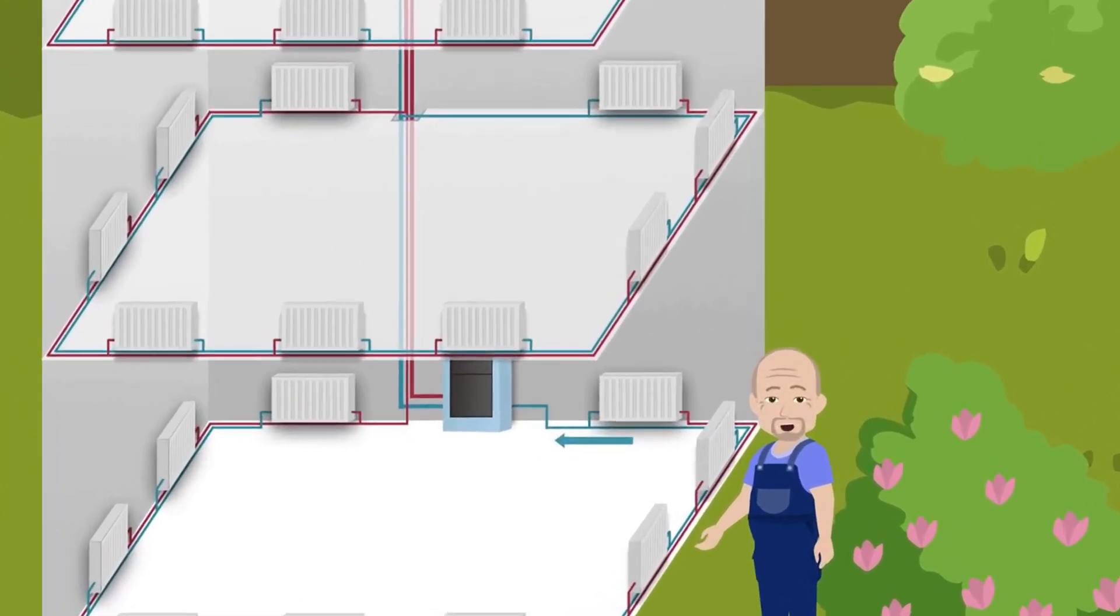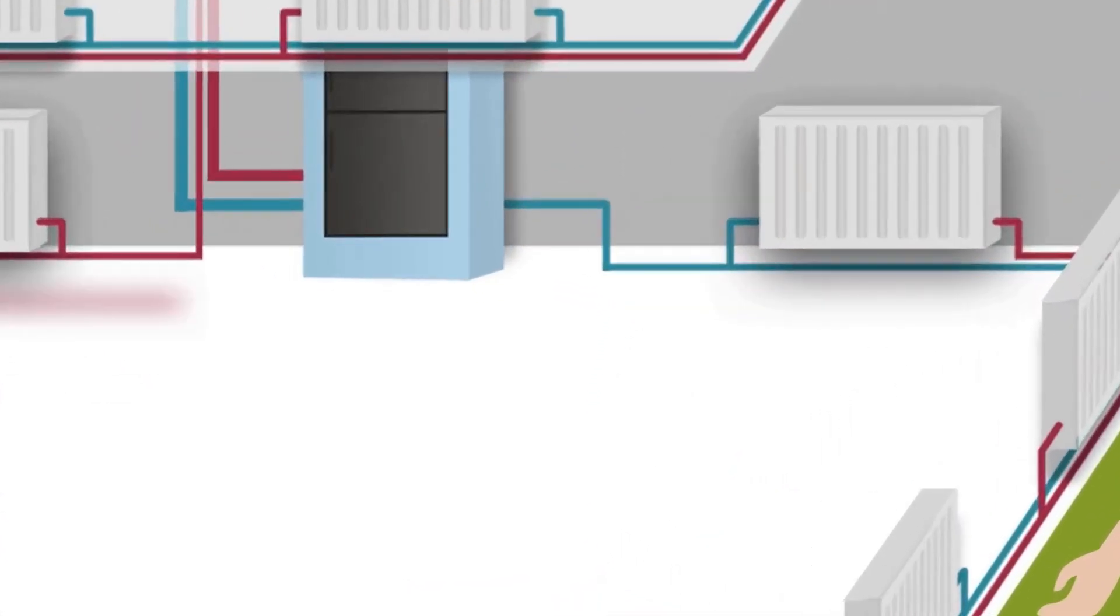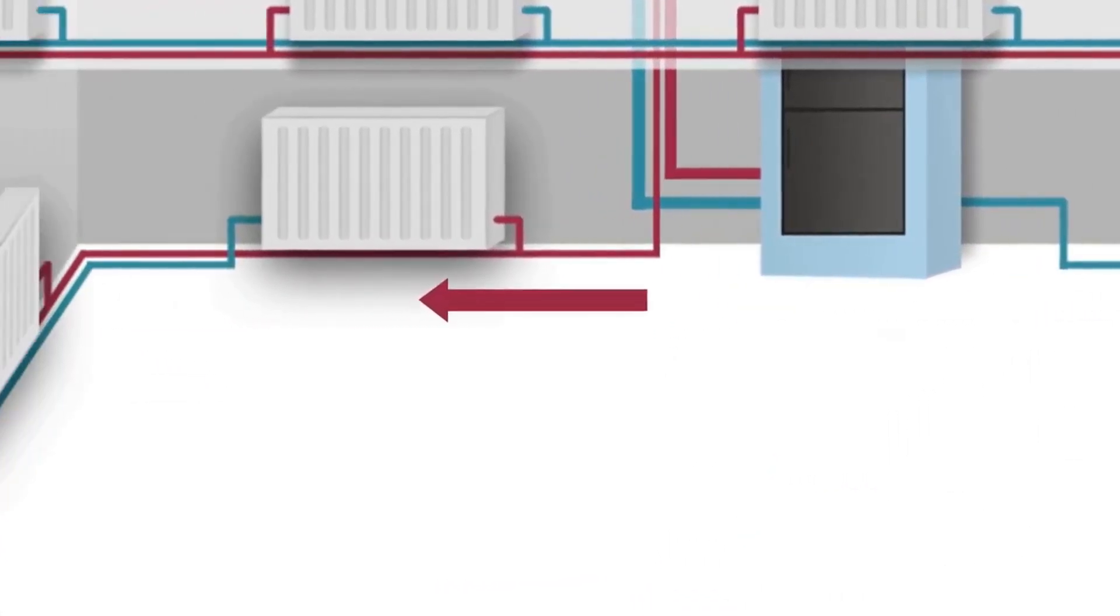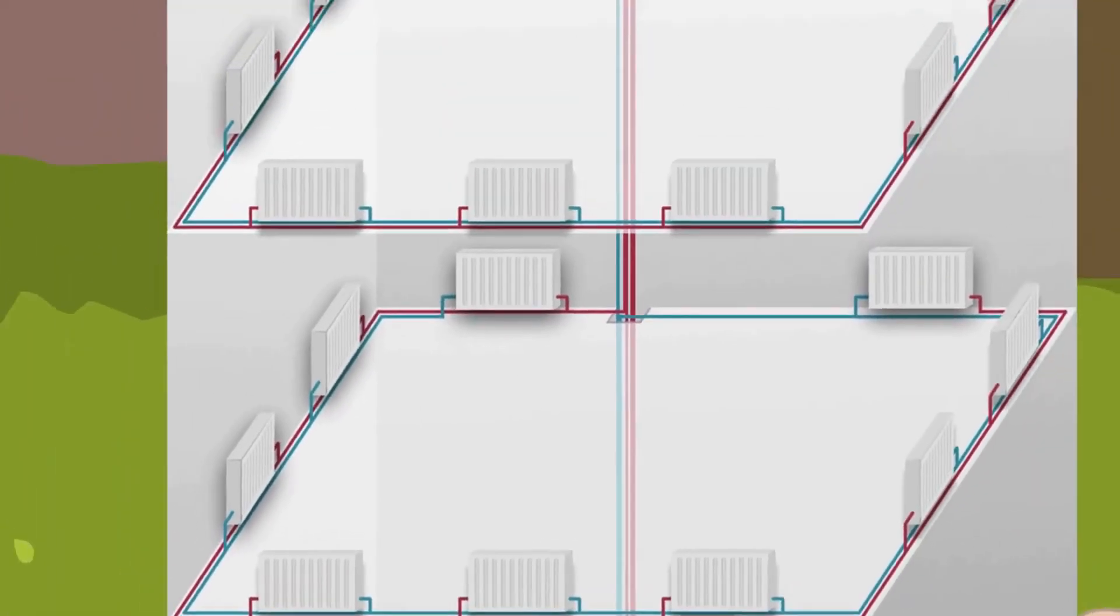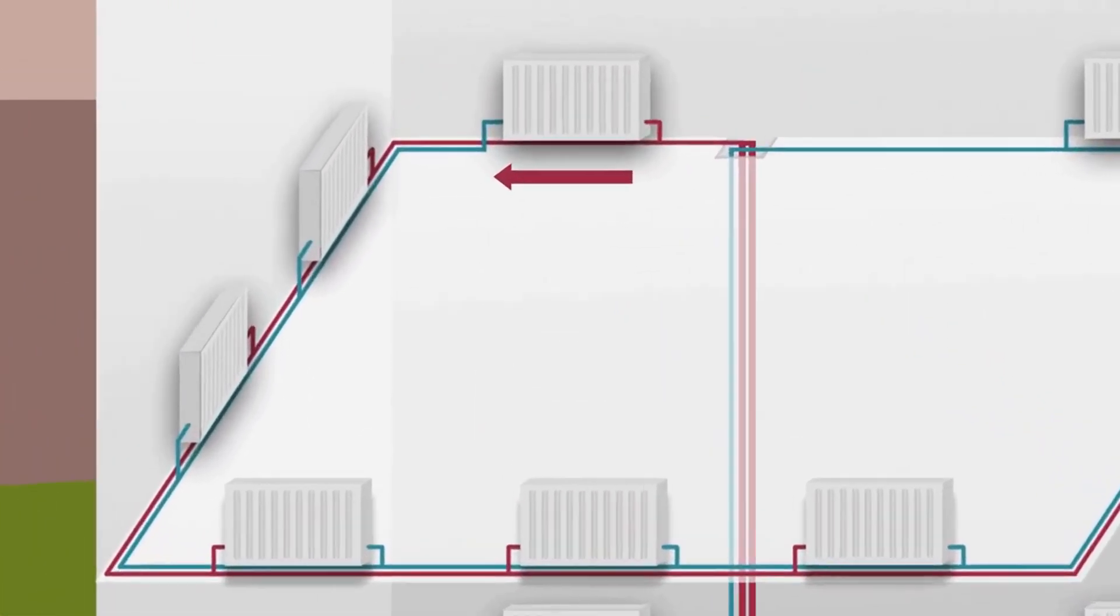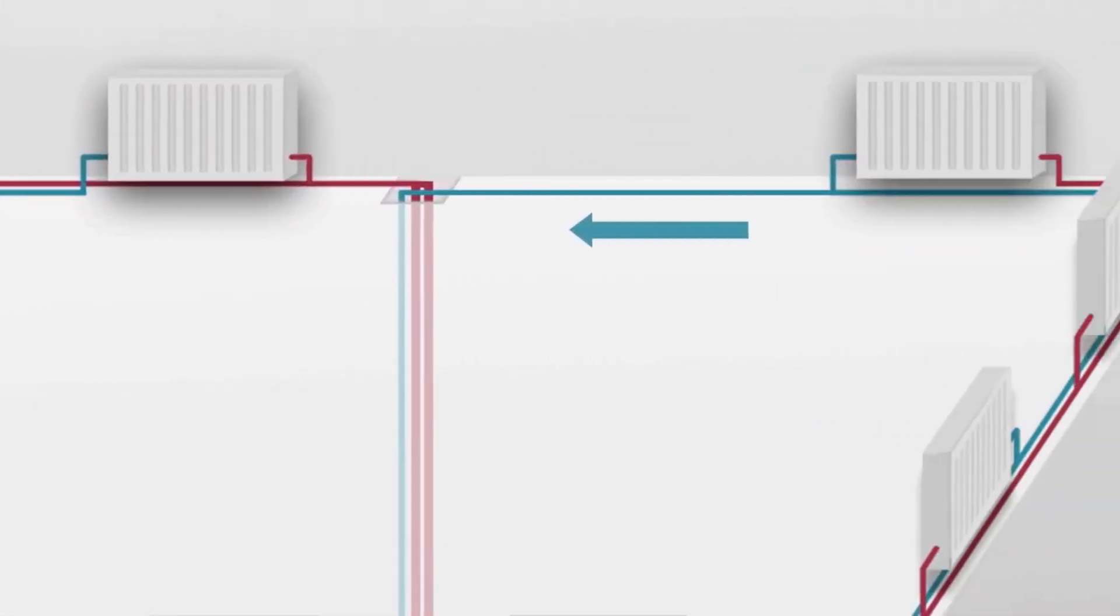It turns out that the first floor is closest to the return, like in this case, but farthest from the power source. The top floor is closest to the supply and farthest from the return.